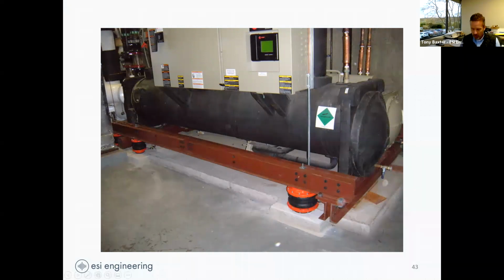Probably close to 75% of the noise problems we troubleshoot in buildings really come back to vibration. It starts from some mechanical source, and the path is usually some vibration path we need to control. This is another example—they're complaining about noise down there, but it's actually a vibration isolation problem.